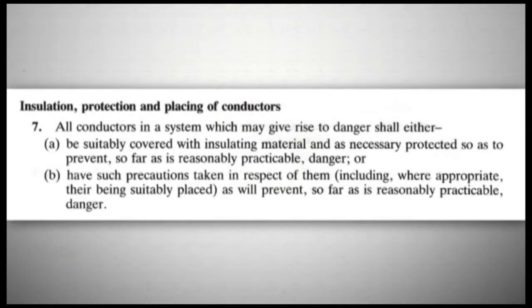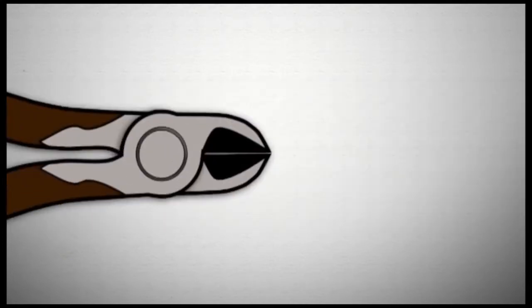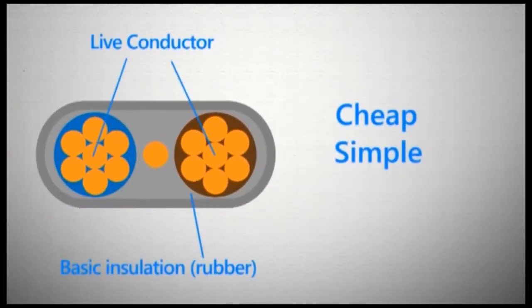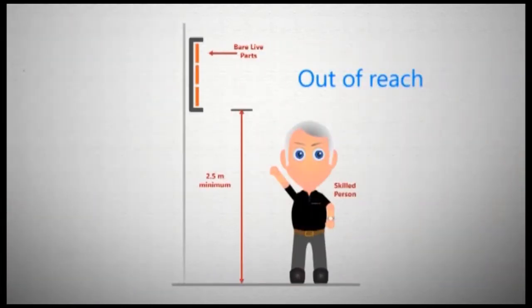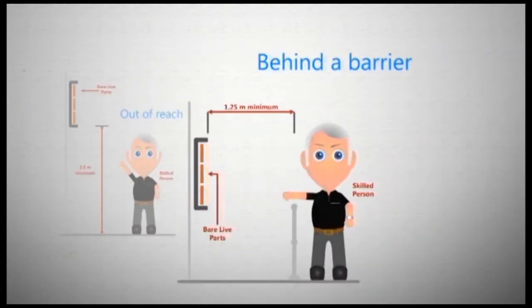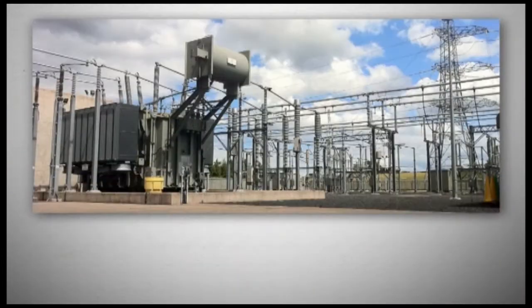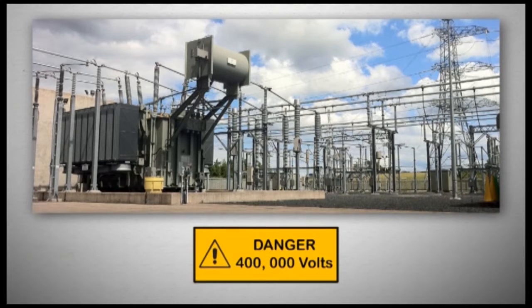Regulation 7 is relatively easy to satisfy. The normal technique is to apply insulation, a simple, cheap and effective solution. Conductors can also be placed out of reach, behind a barrier or at height. For example, here in this substation, 400,000 volt high voltage conductors are not insulated except by the surrounding air, but are high enough off the ground for people to pass underneath without danger.